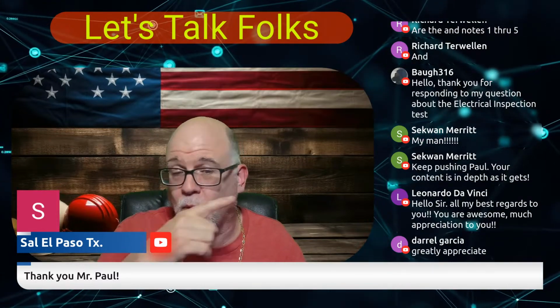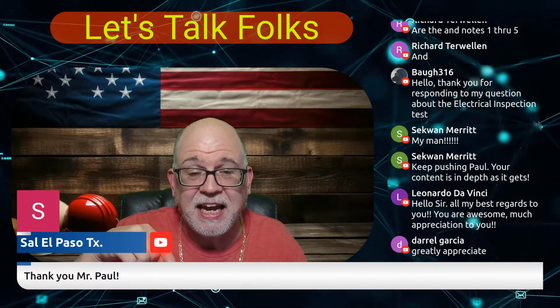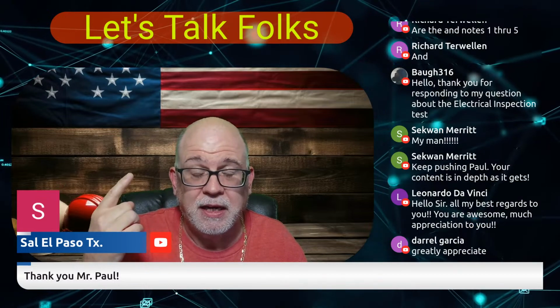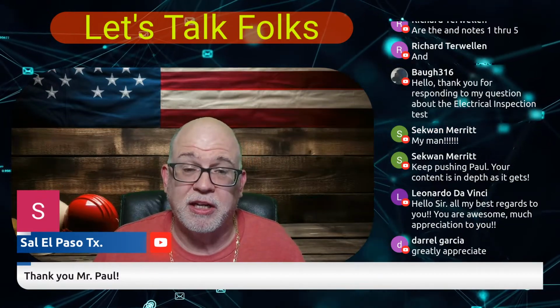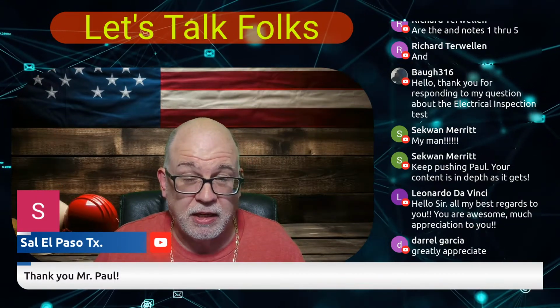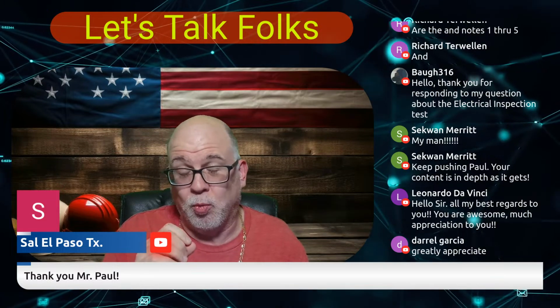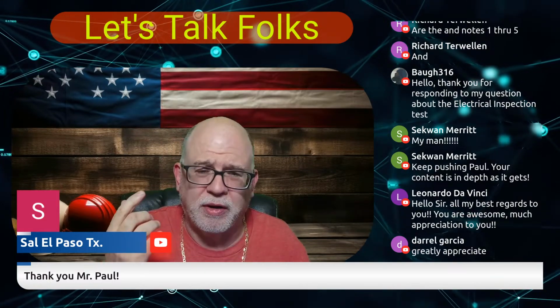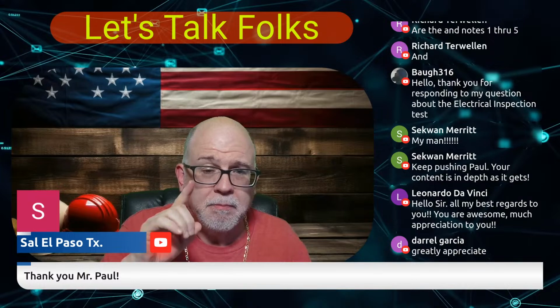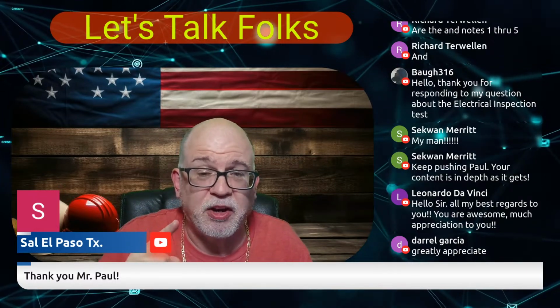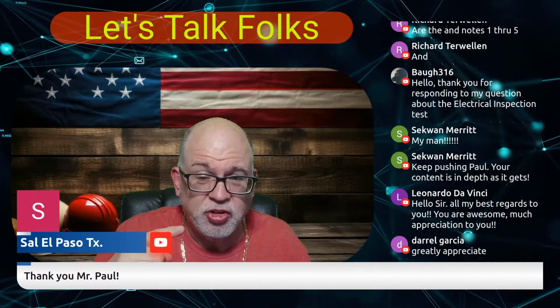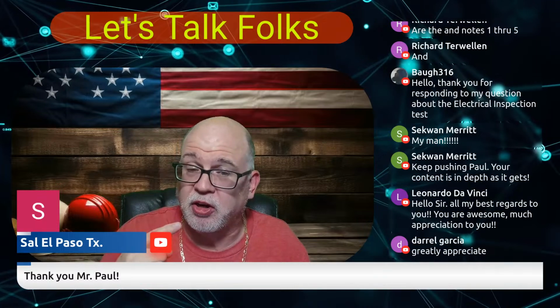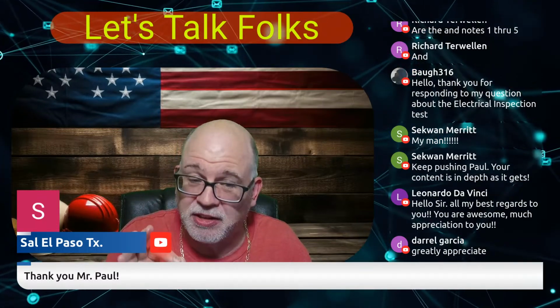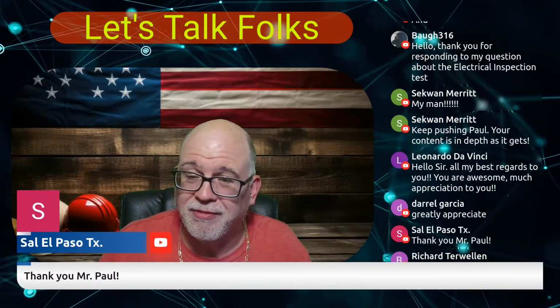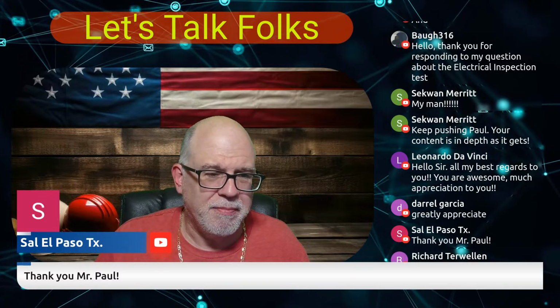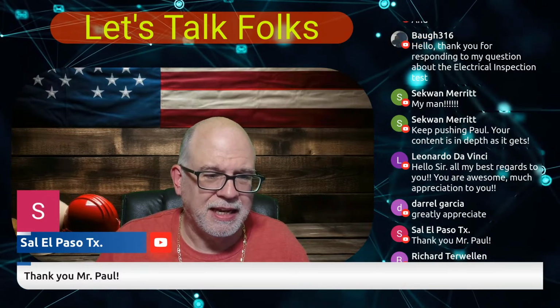And don't forget to go watch my video that's on today at 4 o'clock. That'll be streaming. Make sure you go watch that. That's talking about motor branch circuits, and not the normal, whereas people know that you just do 125% of the FLC. But we want to make sure that you understand that if there is an adjustment or correction due to ambient temperature or more than 3 current-carrying conductors, you've got to take that into consideration as well. So we're going to cover that today. So make sure you check that out, okay?